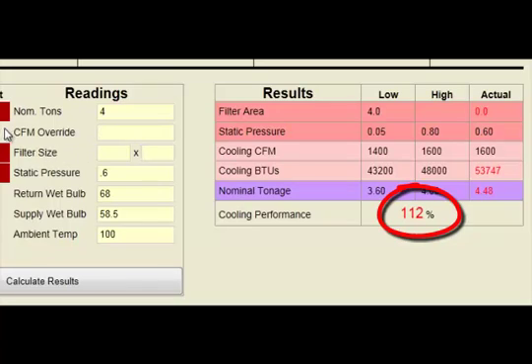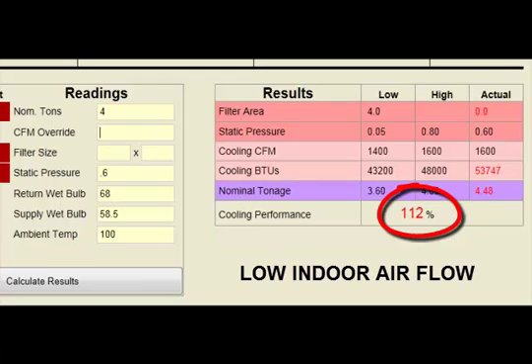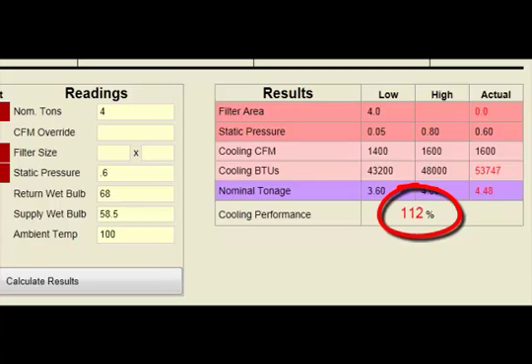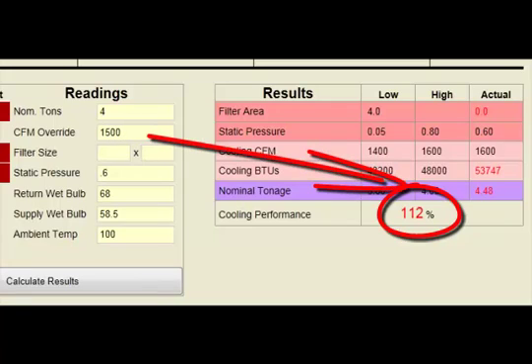Total Performance Diagnostics allows this impossible reading, however, to alert the technician to a particular problem, which is low indoor airflow. It is up to the technician to determine the severity of the airflow problem, and this is where the CFM Override feature becomes very useful.